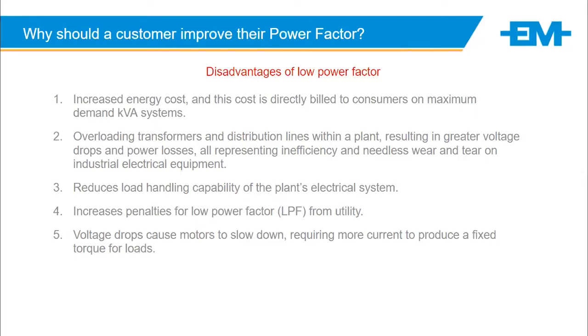A good example is at a customer, I think it was in Botswana. He only had a 500 kVA transformer and was fully loaded, so it was tripping out. He had to wait, I don't know how many months, to manage with the utility to try and get a transformer from council. Now, he couldn't get that going. What he did was a recording and said, I'm actually inefficient. I've got a bad power factor. And putting down a power factor system managed to reduce the demand on the transformer enough to prevent tripping out. So without having to change a transformer, much more cost effective with power factor correction, he managed to resolve that problem. All right.